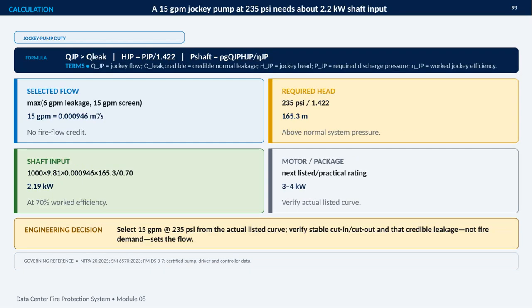This slide works through the jockey-pump duty calculation. The first decision is flow. The pump must exceed credible normal leakage, so we compare 6 gallons per minute of leakage with the 15 gallon per minute screening value. The selected jockey flow is 15 GPM, or 0.000946 cubic meters per second. It receives no credit toward fire flow.